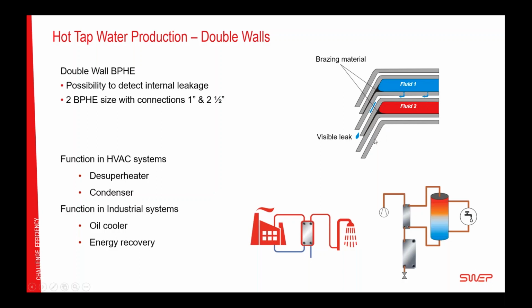Why do you want to do it? Well, the only reason why you want to do it is because of the extra safety that this gives. Because if there is a leak on either side, fluid 1 or fluid 2, and you don't want to mix them because fluid 1 is tap water that you're going to shower in, by using a double wall, you will be able to get this extra visible leak safety, so that before you get contamination, you will be able to identify the leak and exchange a heat exchanger. The applications where it makes sense to use a double wall are as a desuperheater or a condenser for a refrigerant system when you do tap water, or for industrial systems like an oil cooler or different types of energy recovery, where the end usage of the energy is to heat tap water. That was a double wall.